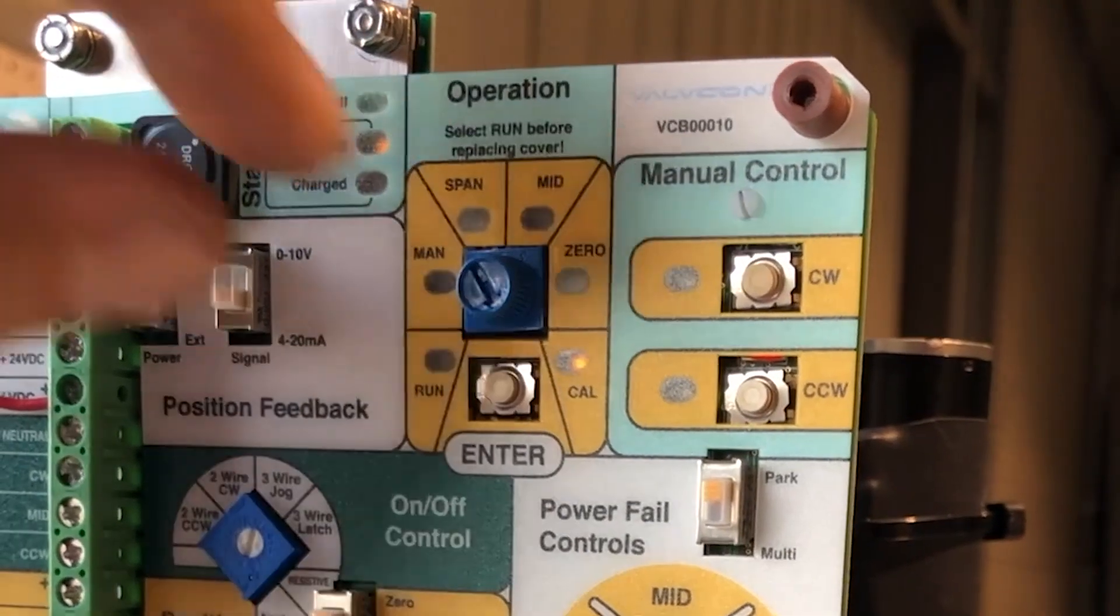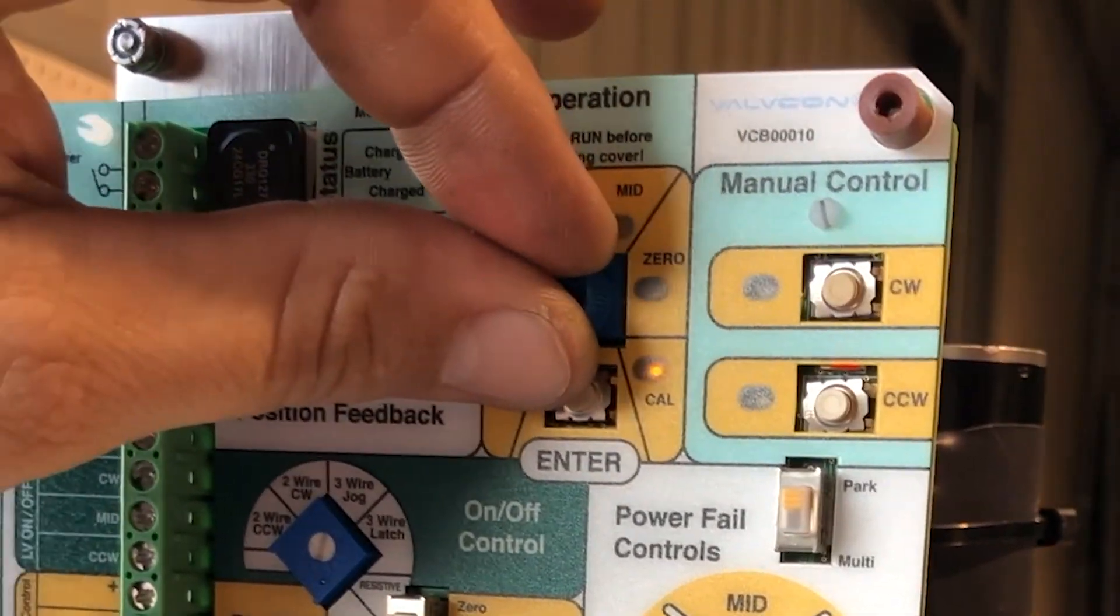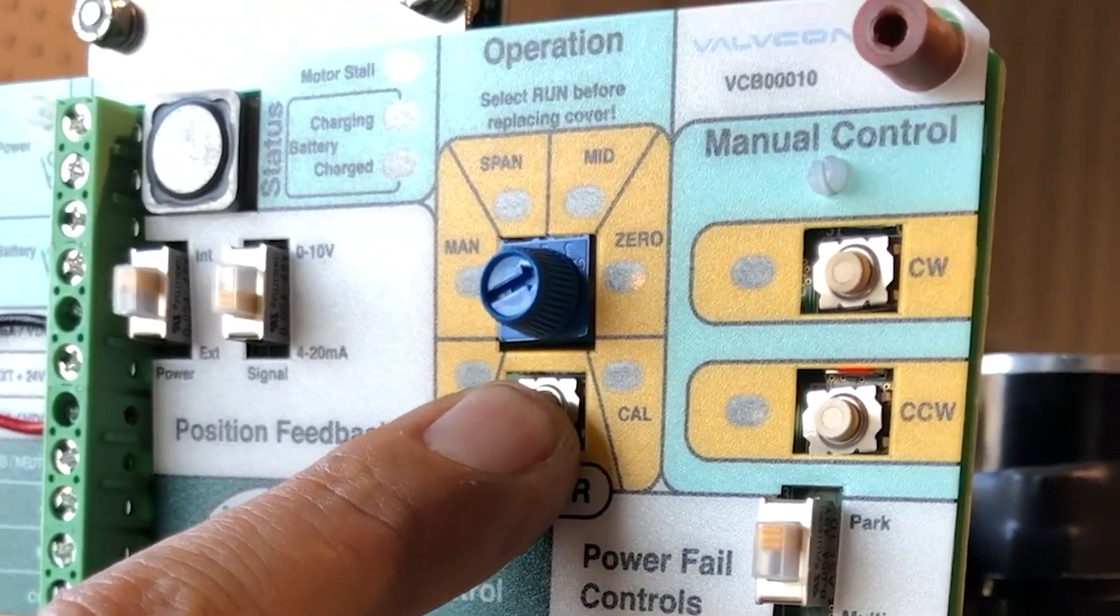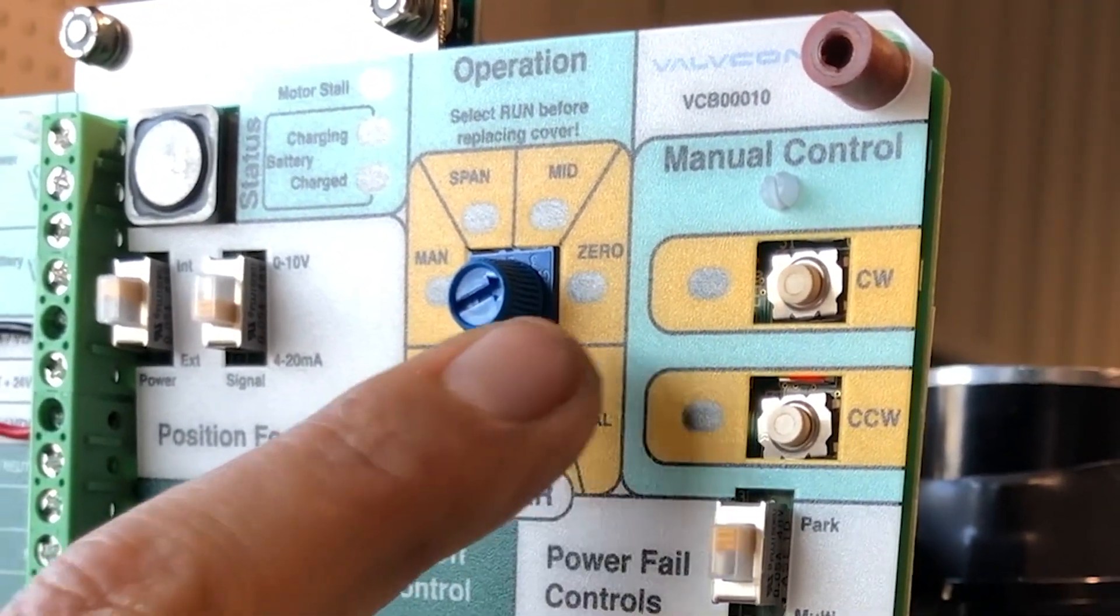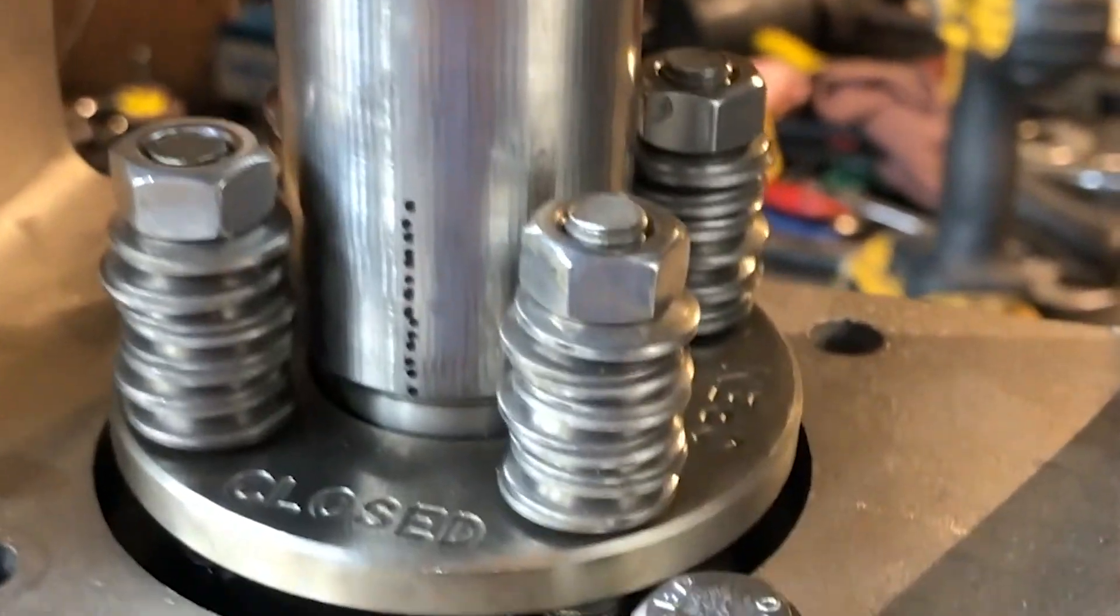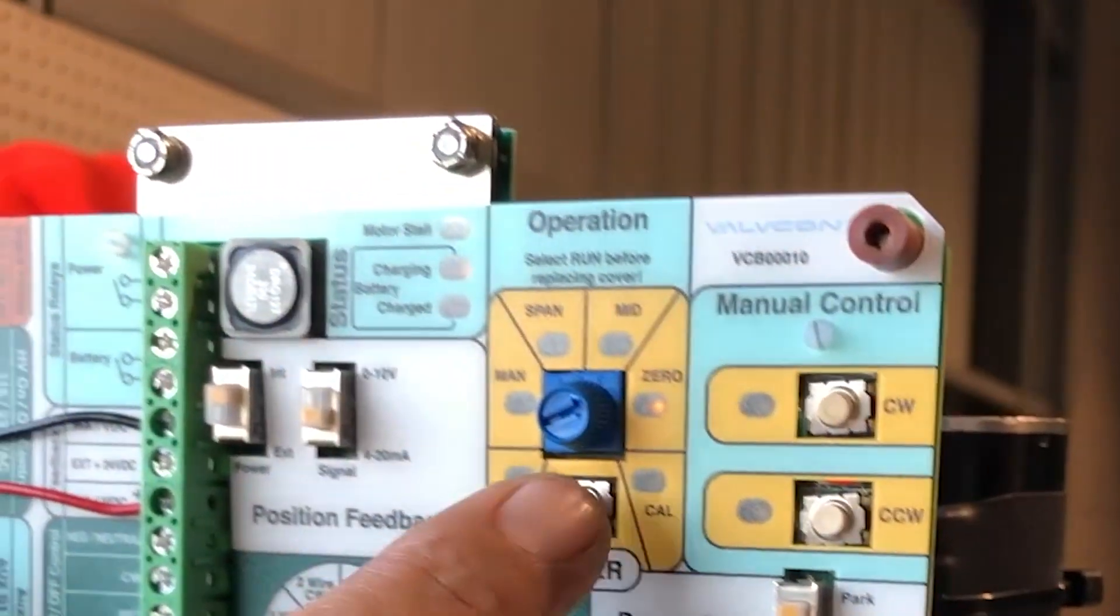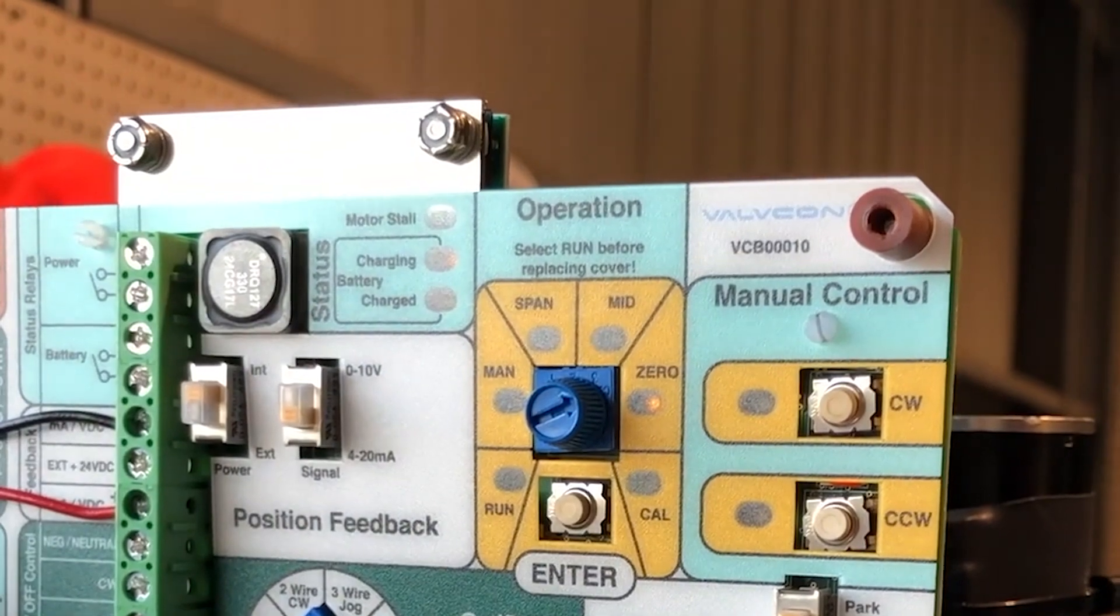Next we want to go to the zero position. Press enter for one to two seconds until we get a flashing LED. Next we want to verify that our valve is in the closed position and that our milliamp signal is at four. Press enter to take the change.